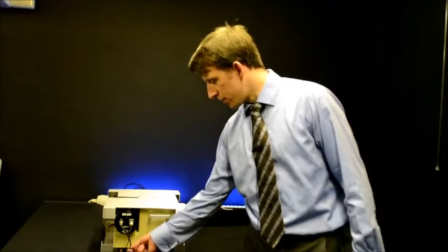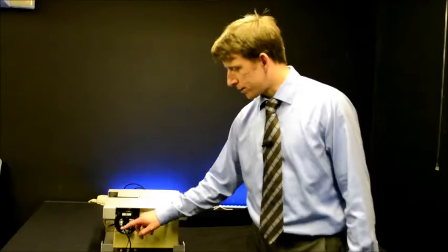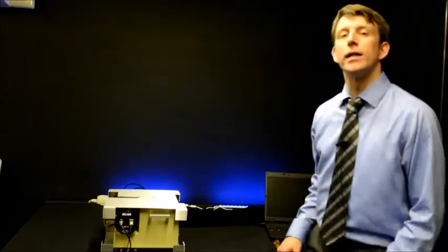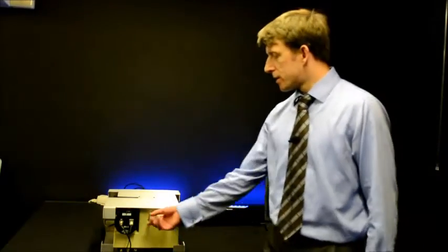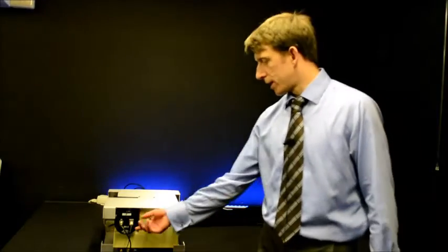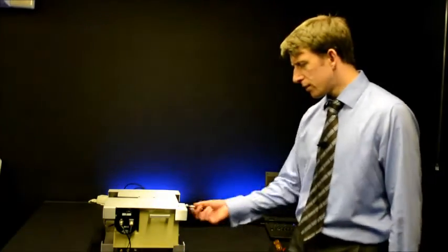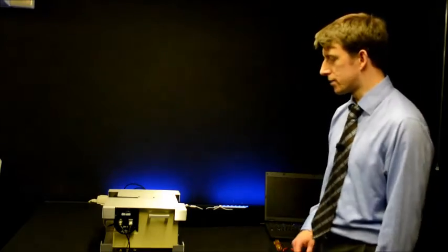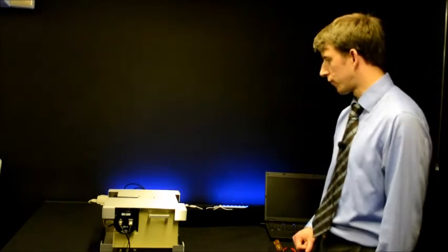This device requires a high voltage for operation, provided by a high voltage supply in the MDE electronics, connected via a thick BNC cable, and there is an on-off switch with a green LED indicator beside it. The signal from the photomultiplier is connected to input 1 next to the high voltage input via BNC to SMA connector cable. The BNC cable is simply connected directly. The SMA connector is pushed on and rotated to ensure it's firmly in place.